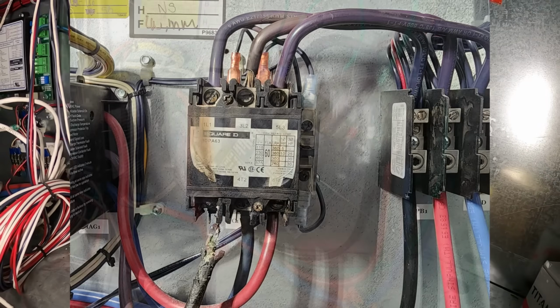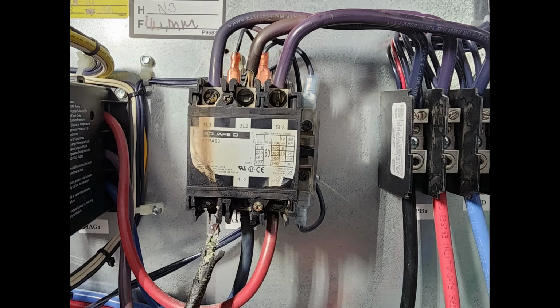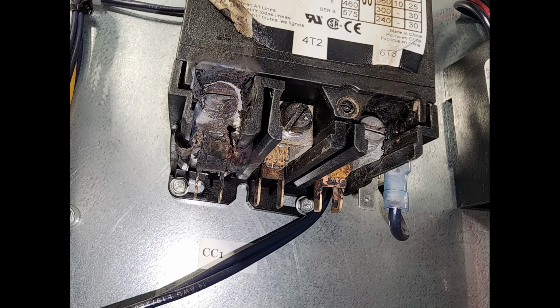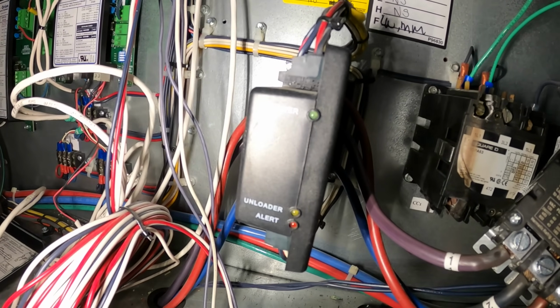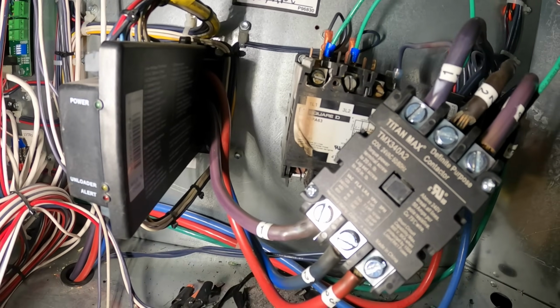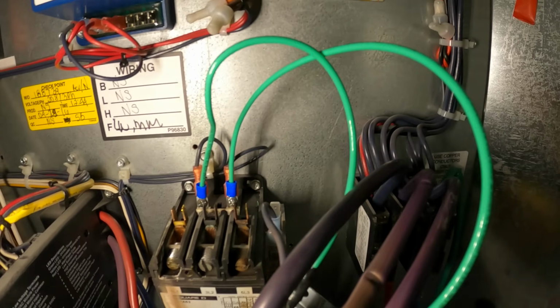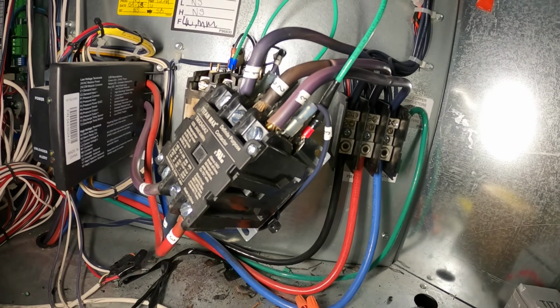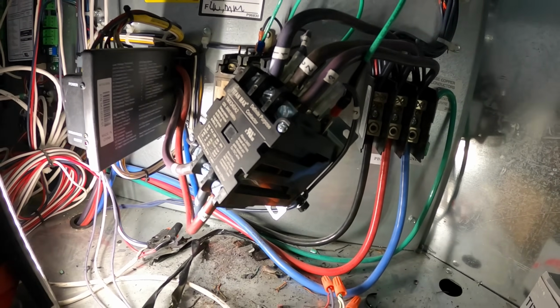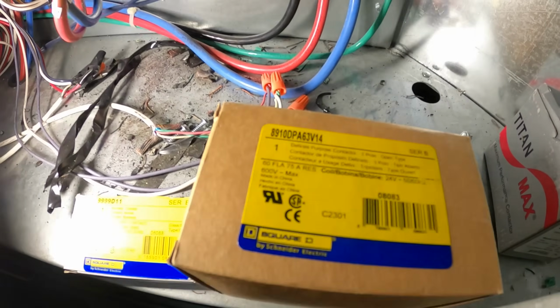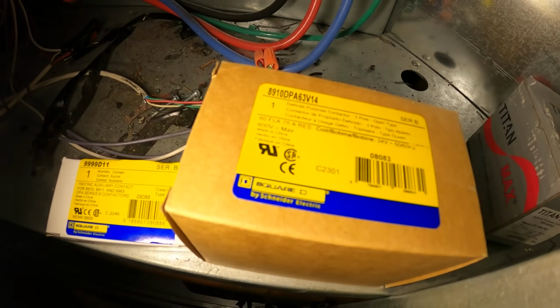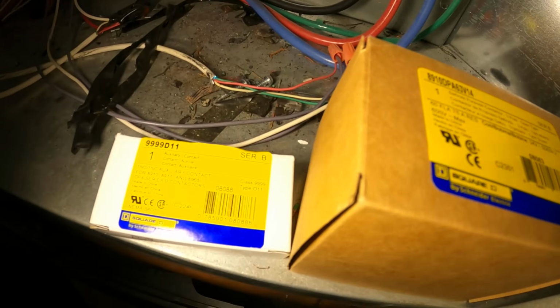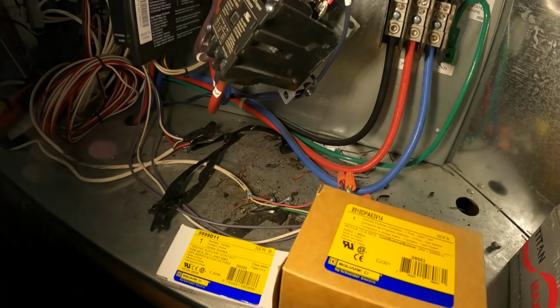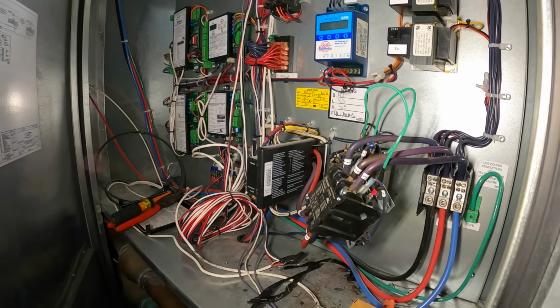I'll show you some pictures. Because the compressor wasn't running, we ran into an alert. One of the wires burnt off and that contactor is completely melted. This is a 60 amp contactor with auxiliary contacts, and I put in a 40 amp contactor, as all I had is a 24 volt coil, and that was just a test. We got it up and running, but now I have the original parts. I got the 60 amp 3-pole contactor with 24 volt coil and our auxiliary contacts. So today we're going to be putting that back in and starting this thing up.